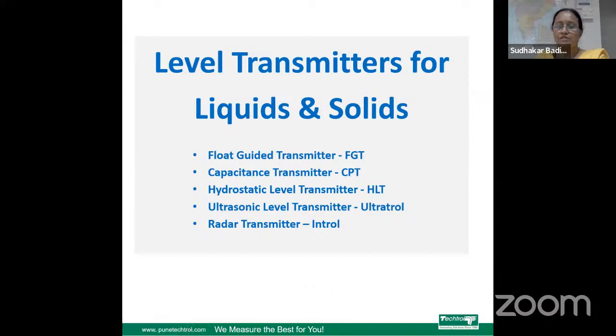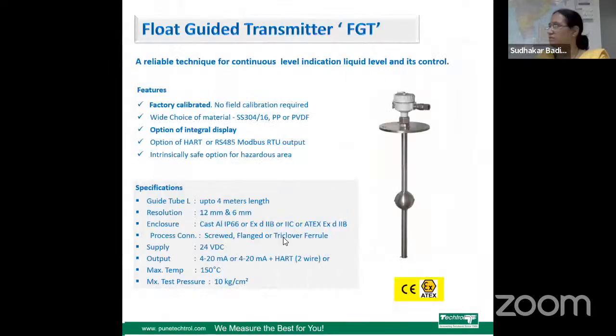So the switches part is over. Now let us see level transmitters for liquids. These are the float guided level transmitter, capacitance transmitter, hydrostatic level transmitter, ultrasonic level transmitter, and radar level transmitter. Okay. So this is a float guided transmitter, generally used for continuous level indication. It is factory calibrated and you can directly mount it on the tank. A wide choice of material is also available. You will get 4 to 20 milliampere output through this transmitter.